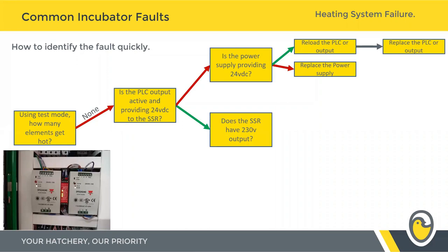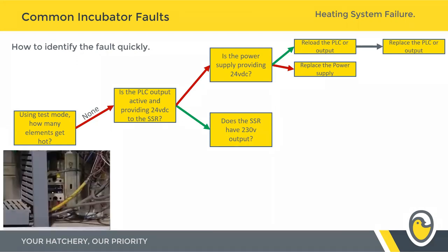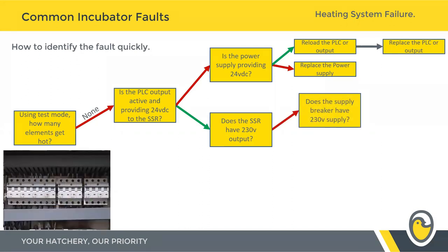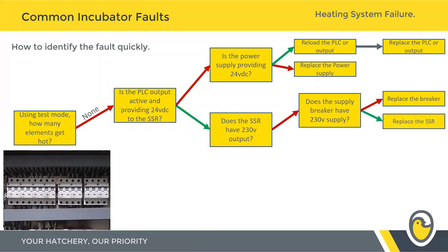If the PLC output is supplying 24 volts to the solid state relay, look at the secondary side of that solid state to check it's got 220, 230, or 110 volts going out to the heating elements. If it doesn't, check the breakers — make sure it's on, check the wiring for loose connections, and make sure you've got a clean 230-volt supply. If you don't, replace the breaker. If you do, replace the solid state relay. Within five steps, you've narrowed down the fault on the incubator to exactly what it is.